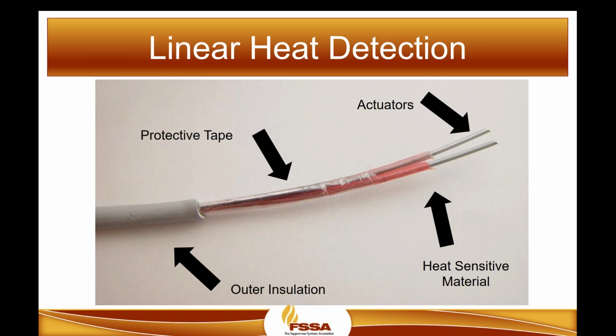As far as testing, you can run the cable inside the hazard, bring it back outside, and have a testing point. It's a very cost-effective product and installation for the coverage it provides. We use it in hangars where spacing and height concerns, as you mentioned, are a problem. Some of the disadvantages: it is easily susceptible to damage. That's been the problem. That has caused false alarms with kinking or shorting the cables together. But if properly installed, it does very, very well.